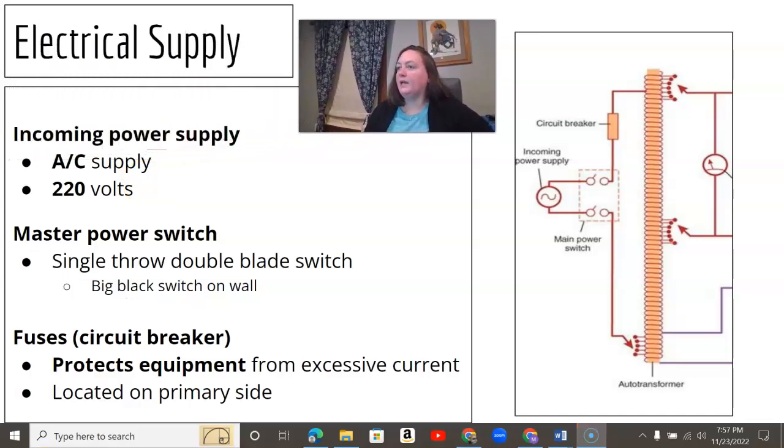Your electrical supply, the incoming power, is alternating current, and all three of your transformers also work off of alternating current. So it's AC coming in, and about 220 volts is your incoming power. You have a main power switch, which if you've looked at any of your x-ray rooms, there's a big black switch on the wall. And then there's fuses and a circuit breaker here to protect your equipment from excessive current, all located on the primary side.